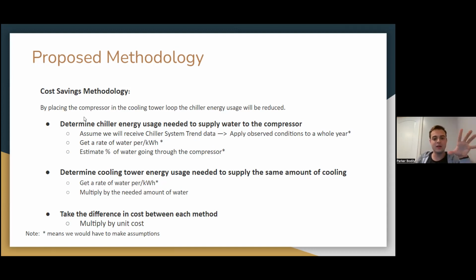So what we're thinking is you can get a rate of how many kilowatts it takes to cool down the water in your chiller, like the energy from gallons per minute per kilowatt hour. And then from there, you can tell how much energy goes in to cool the water. And then we can estimate how much water is actually going to the process and how much of that chilled water is going to that one compressor, because we don't want to change the cooled water going to the process, only to the compressor.